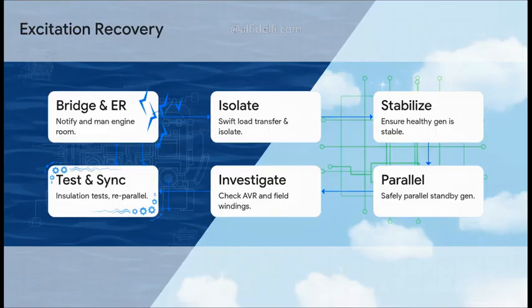Once the bridge is notified, your top priority is a swift load transfer and isolation of the faulty breaker. You are basically surgically cutting out the sick machine while the healthy one seamlessly takes over the load. Once that healthy generator is stabilized, you can safely parallel a standby generator because, well, your bus is secure. With the ship fully powered, you can then safely investigate the AVR, perform insulation tests, and eventually re-parallel the repaired unit. Notice the huge difference here? Handled correctly, the lights never even have to go out.